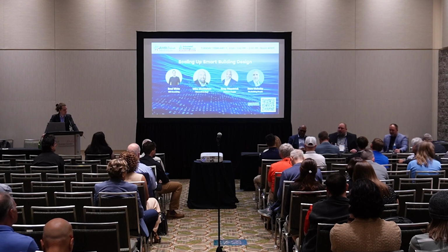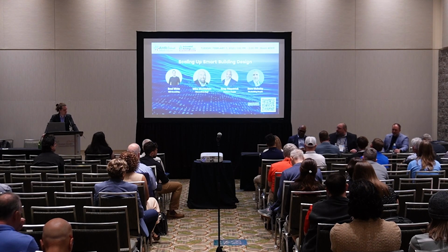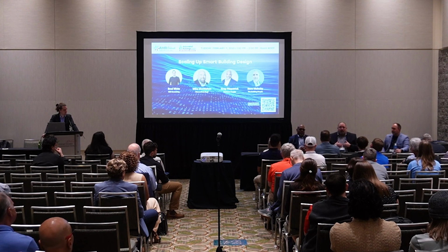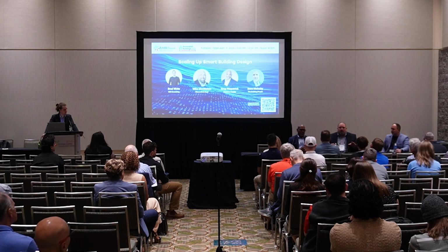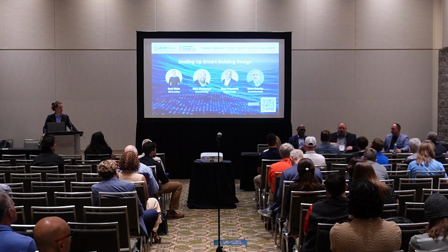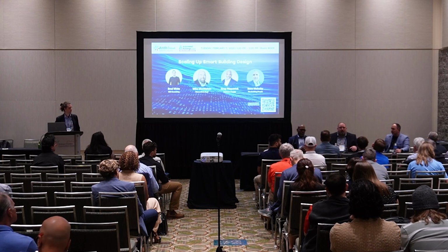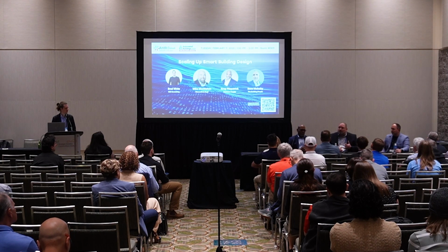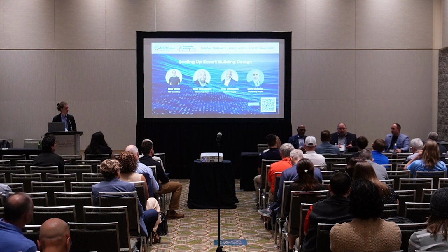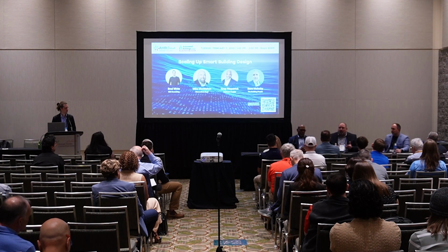So if you go at it from a risk standpoint, an MEP that doesn't do cybersecurity now says, well, I'm not going to do it because it's a liability for me to include that. But what we're introducing now is that basic cyber hygiene process where I say, all right, system integrators, you don't need to incur any extra cost or up your bill because you have to bring in a cybersecurity expert to install controls. But what I'm going to ask you to do is don't use admin as a username. Change your passwords from the defaults. Very, very simple things like that, right? Turn on logging on the machine.